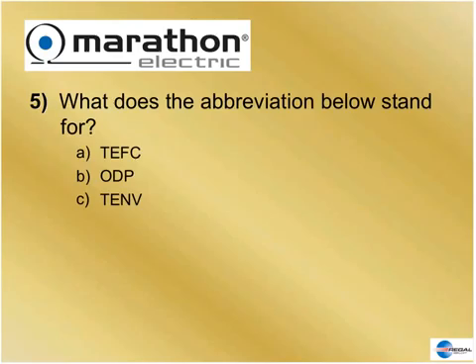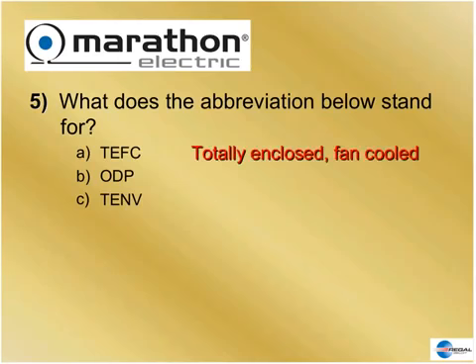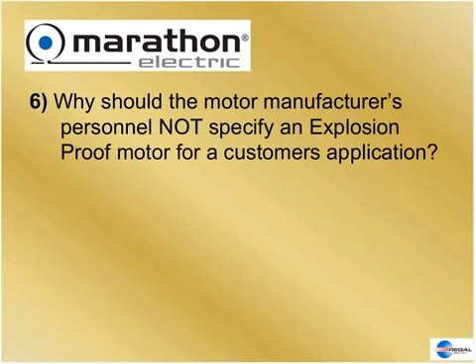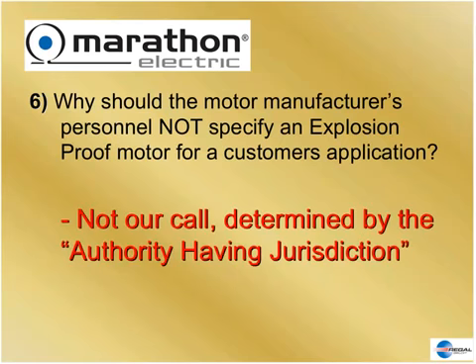Of these enclosure abbreviations: TEFC means totally enclosed, fan-cooled. ODP means open drip-proof. TENV means totally enclosed, non-ventilated. Why should motor personnel not specify an explosion-proof motor for a customer's application? It's not our call — the authority having jurisdiction over that installation and startup makes that specification. It could be a safety engineer, insurance engineer, consulting engineer, Corps of Engineers, fire marshal, or city engineer. Whoever has that authority makes the call.